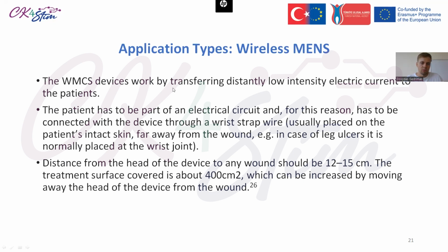This wireless microcurrent stimulation device works by transferring low intensity electrical current distantly to the patient. The patient has to be part of an electrical circuit, and for this reason has to be connected with the device through a wrist strap wire, usually placed on the patient's intact skin, far away from the wound. For example, if there is a leg ulcer, it's normal to place it on the wrist joint. The distance from the head of the device to any wound should be 12-15 centimeters. This is the optimal distance from the device to the body. The treatment surface covered is about 400 square centimeters, which can be increased by moving the head of the device away from the wound. But it should be noted that the farther away the device is, the weaker the effect of the stimulation will be.